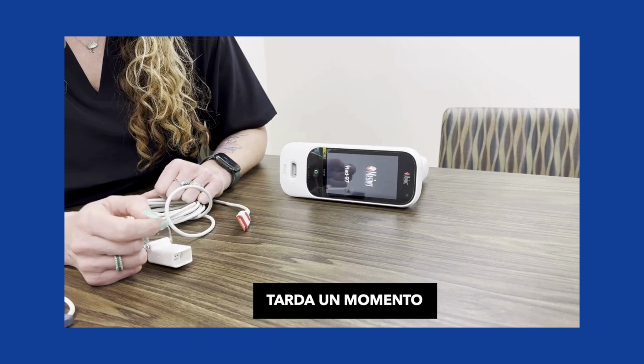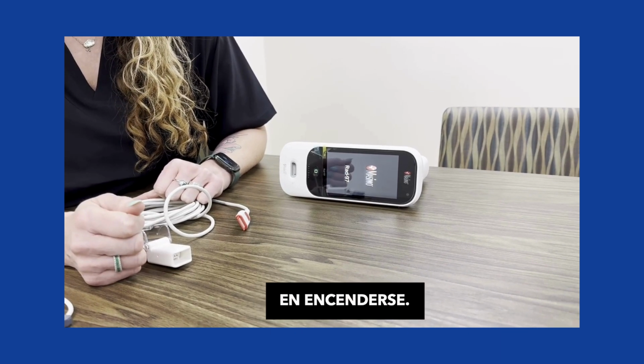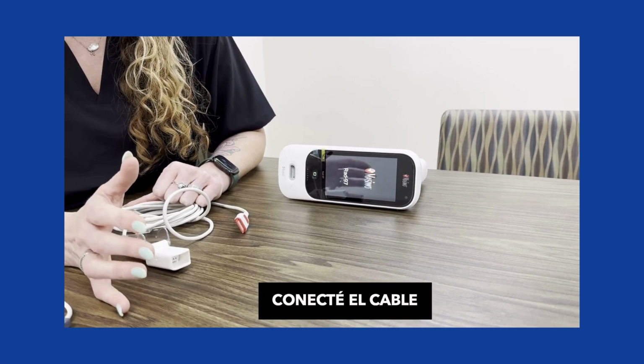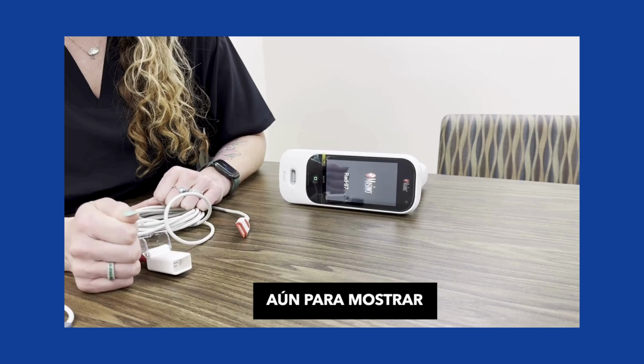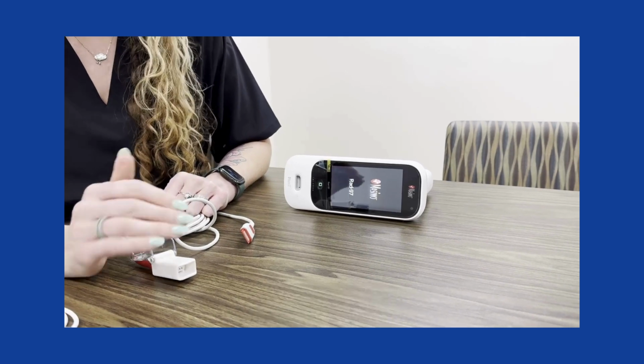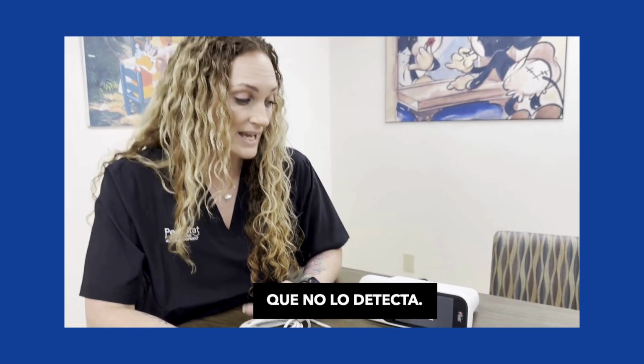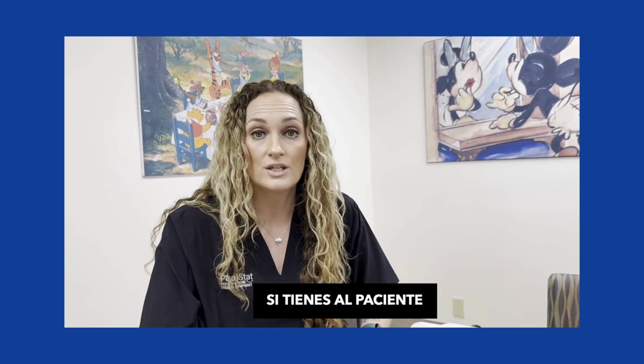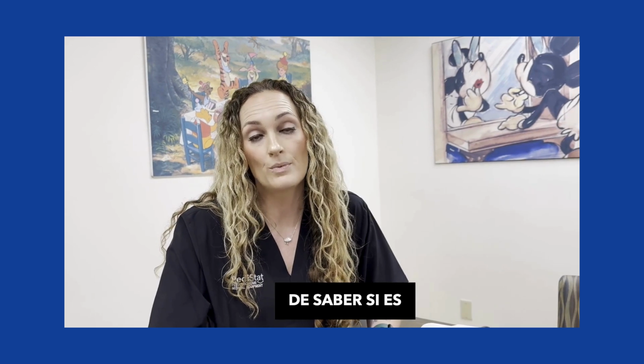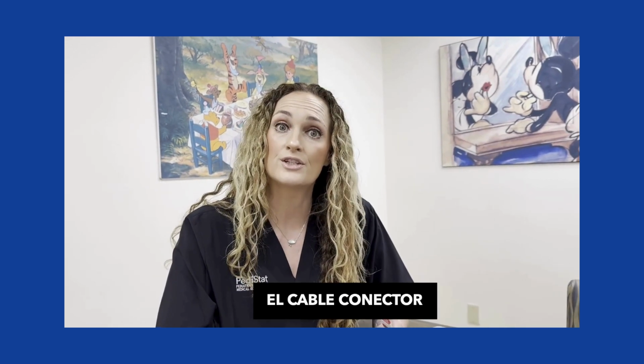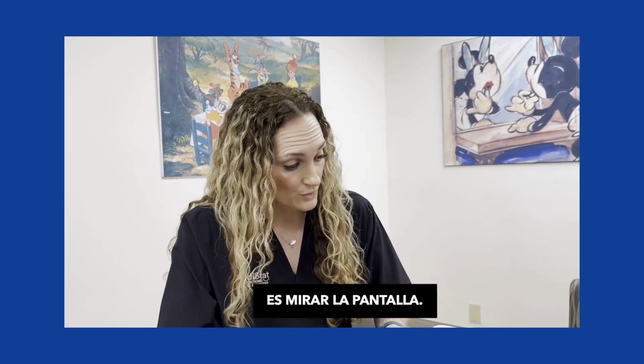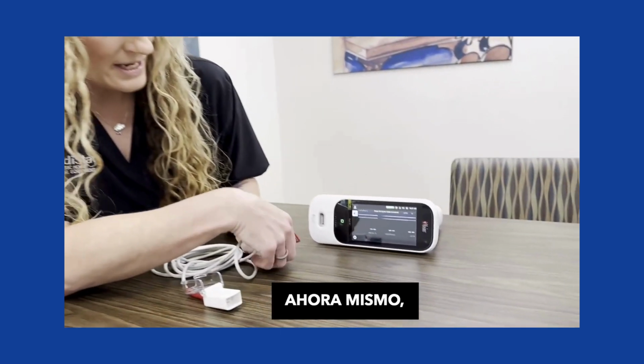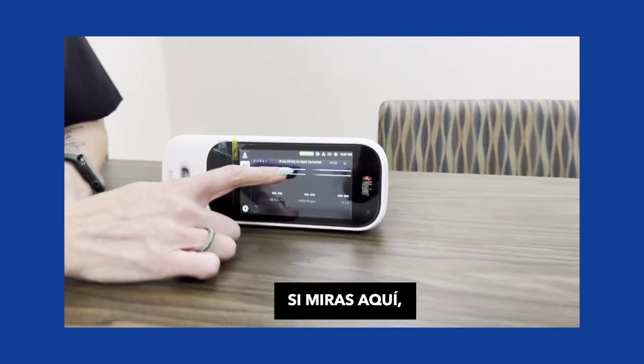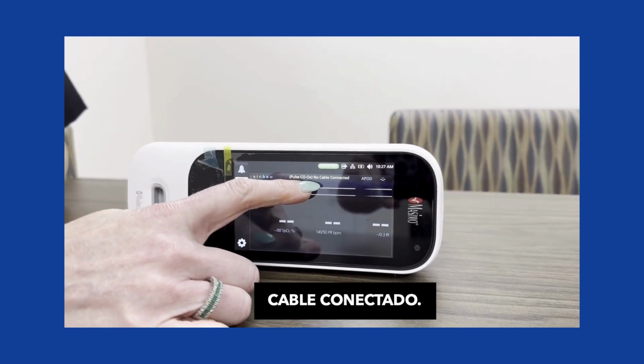So it takes just a second to power up. And the reason why I don't have the connector cable plugged in yet is because I want to show you that it will actually tell you that the machine does not detect the connector cable. That way, if you have your patient on this device and you feel like it's not getting a reading, the best way for you to know if it's the actual connector cable itself is if you read the display. So right now, if you look here, it tells you that there's no cable connected.